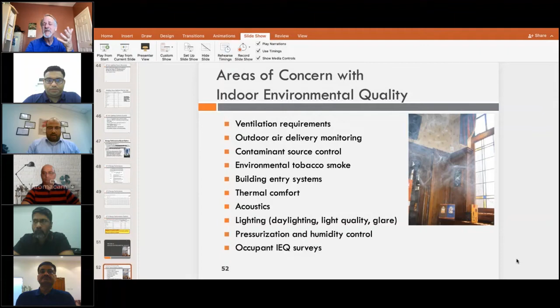Looking at some of the mandatory portions of this: the overall ventilation rate is designed per ASHRAE Standard 62.1, but ASHRAE has also produced Standard 170 for healthcare facilities. In a hospital, medical facility, nursing home, or long-term care facility, controlling the ventilation and the pressurization balance between certain room types is extremely important.